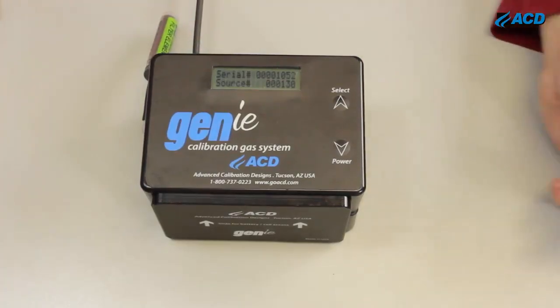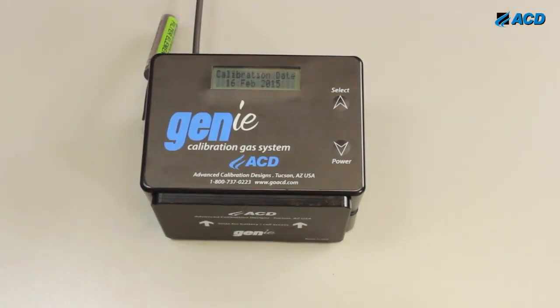It shows you the serial numbers, the manufactured and calibration dates of not just the base unit but also the source. All right, and it defaults to the last concentration and flow rate that the unit's been run at. So whoever ran this unit last had it set to 20 parts per million, 0.5 liters per minute flow. I can set the output anywhere between 0.5 and 50 parts per million, and I can set the flow anywhere between 0.2 and 1 liters per minute.